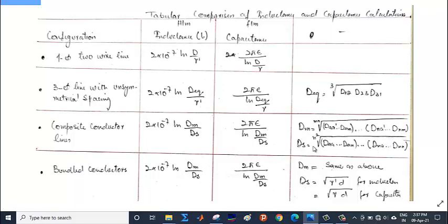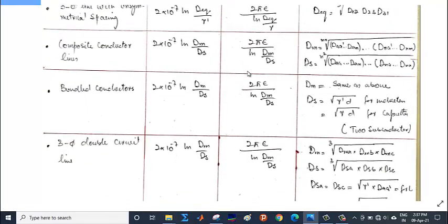Similarly, ds will be equal to the n squared root of daa' up to dan, and finally up to dna' up to dnn. These are the self distances of all the conductors from its own subconductors or substrands.